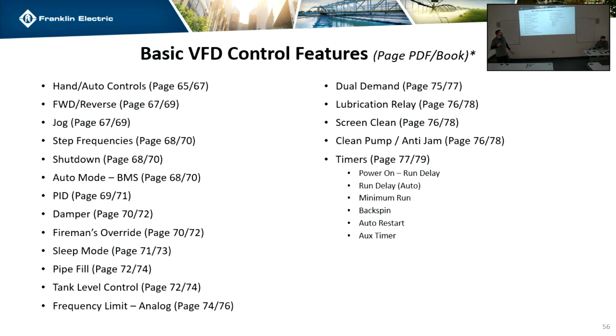The direct PID is more for pump applications. So as the pressure goes up, the drive's going to slow down. HVAC's opposite. So we have PID inverse, right? Okay, so that's the same here as well? It's in here.